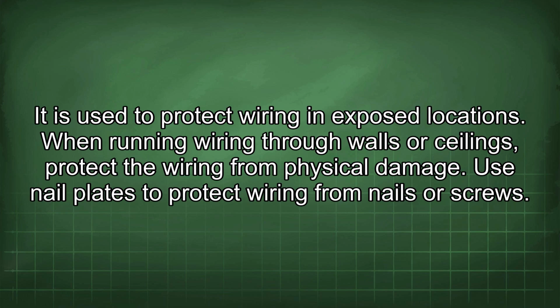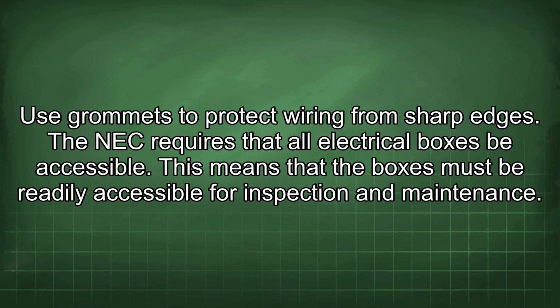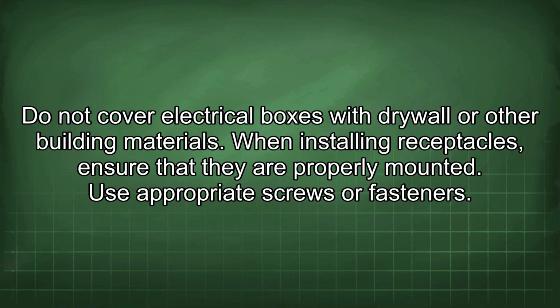When running wiring through walls or ceilings, protect the wiring from physical damage. Use nail plates to protect wiring from nails or screws. Use grommets to protect wiring from sharp edges. The NEC requires that all electrical boxes be accessible. This means that the boxes must be readily accessible for inspection and maintenance. Do not cover electrical boxes with drywall or other building materials.